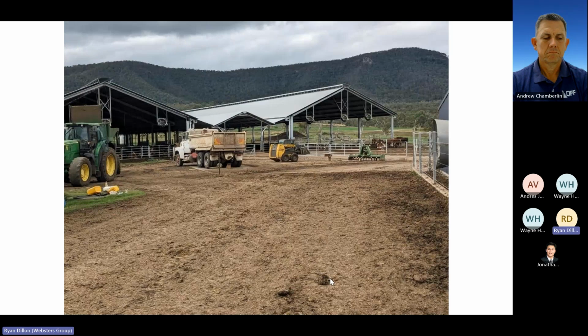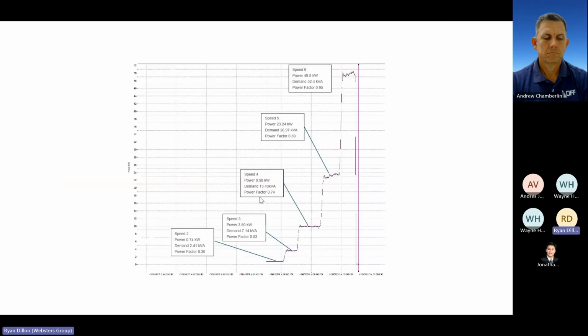So in this instance, you can see on the right-hand side, here's the fan here, if you follow my cursor, and there's a number of fans all the way back through these sheds. So we tested those, and there's a speed controller associated with these fans. So in this instance, when they're at full speed, each barn used close to 50 kilowatts. I'd mentioned peak demand, quite often measured in kilovolt amps, and the power factor for those energy nerds was 0.95.